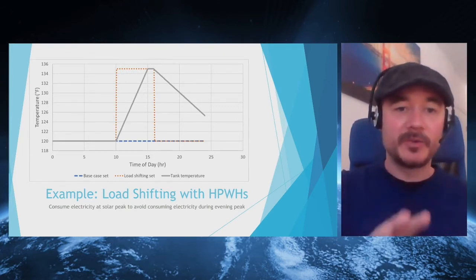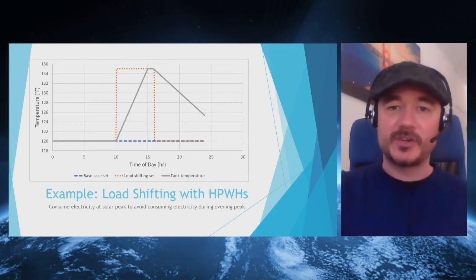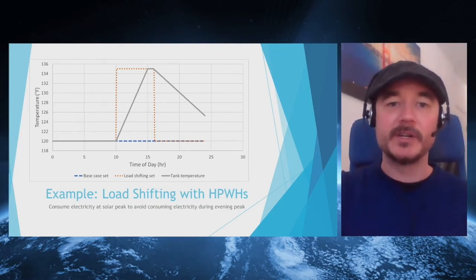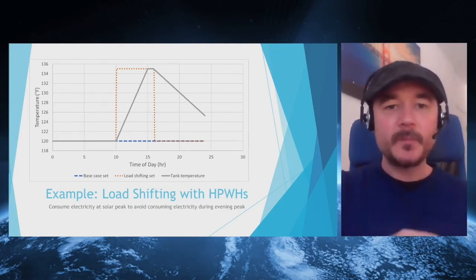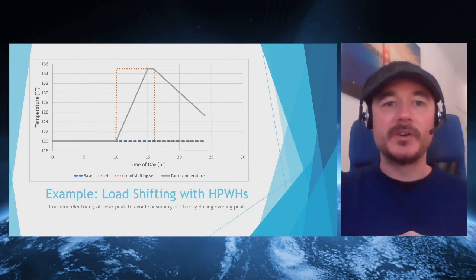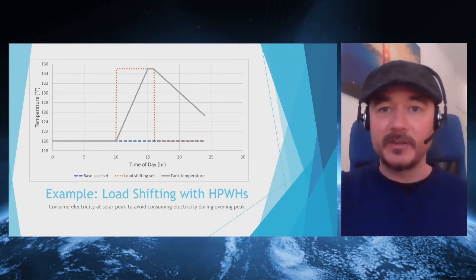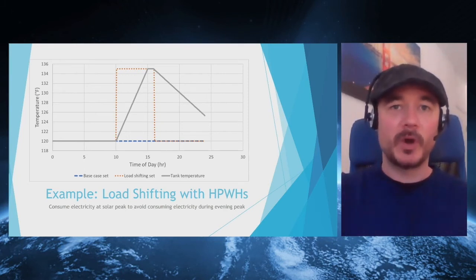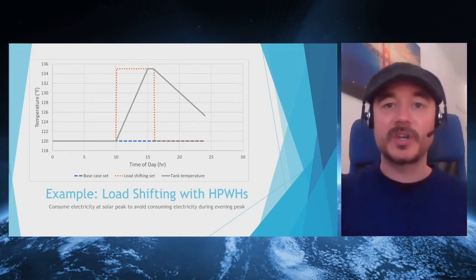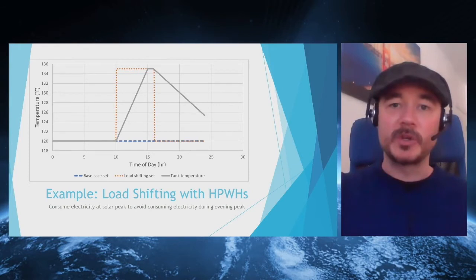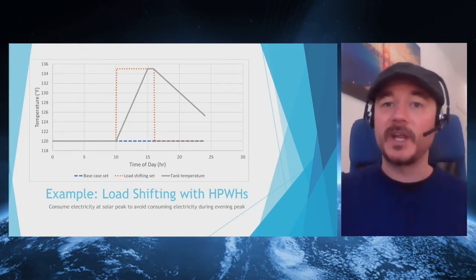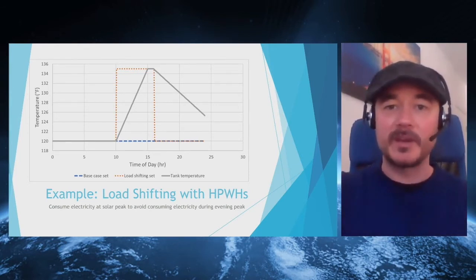This plot shows how we're trying to change the control of a heat pump water heater to take advantage of that. Keep in mind, water heaters are very reactive devices, especially storage type water heaters with a big storage tank of hot water. The device keeps it at the set temperature. You consume hot water, the water gets colder, and it heats the water back up to the set temperature. That's all it does.